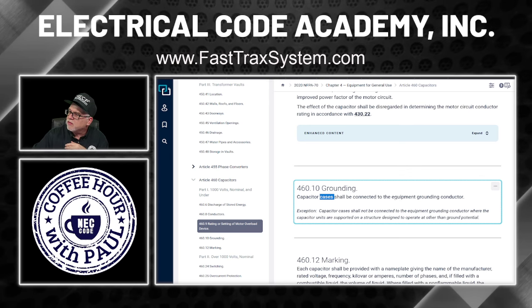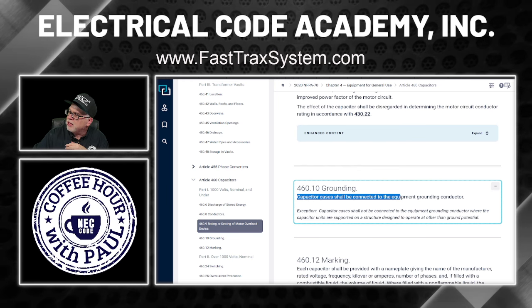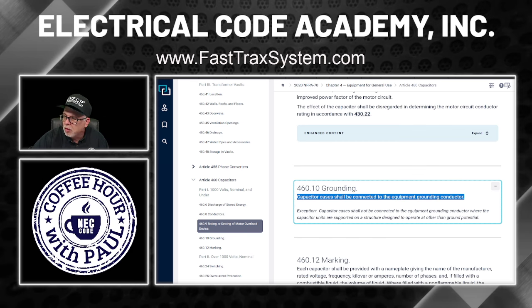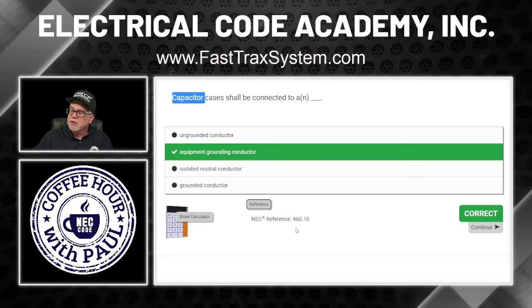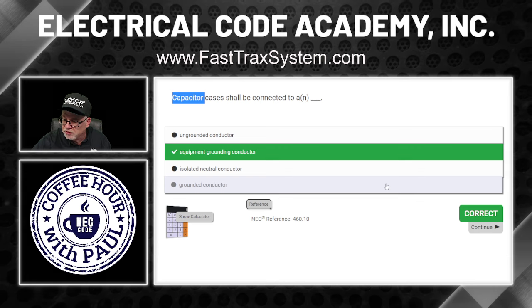So, what does it say? Capacitor cases shall be connected to the equipment grounding conductor. It seemed like that should have been common sense anyway, right? So we'll kind of go back and equipment ground, and there's our reference. 460.10. Okay? Folks, it's really just that simple.